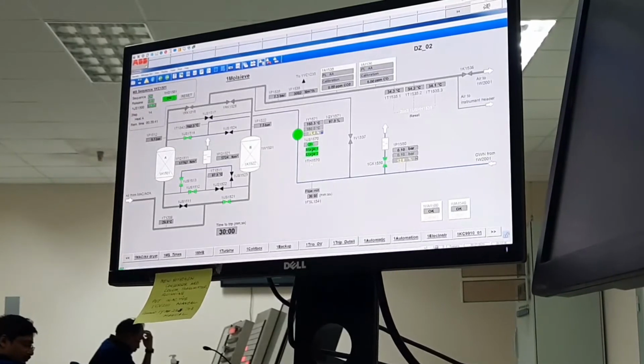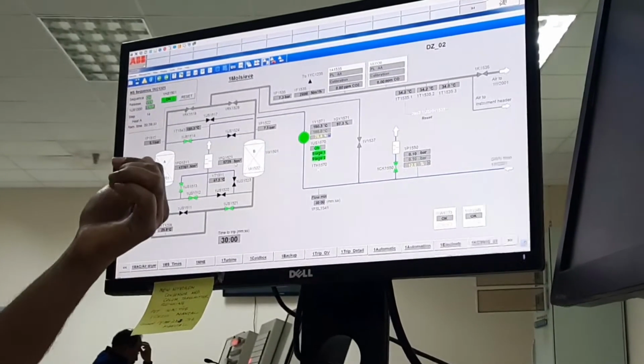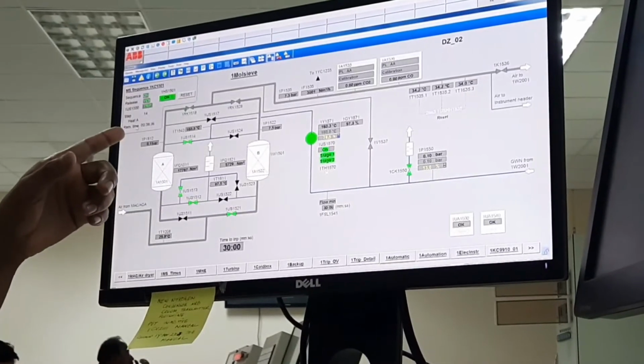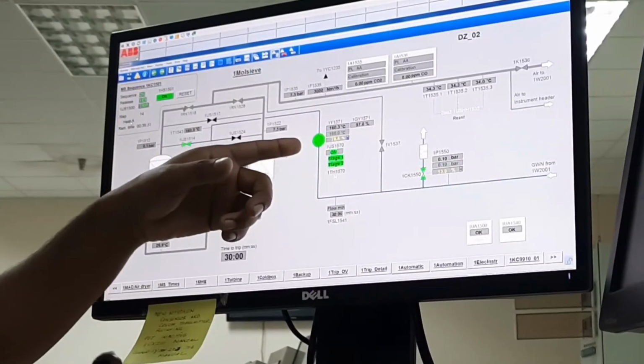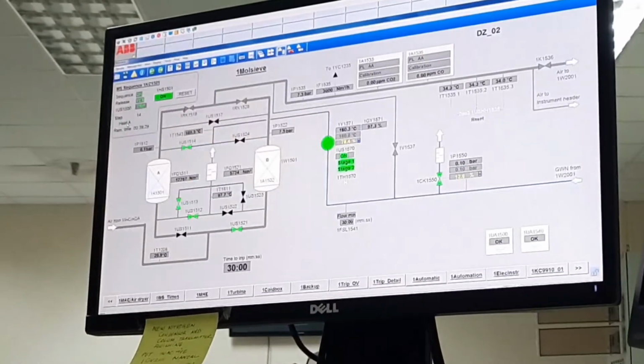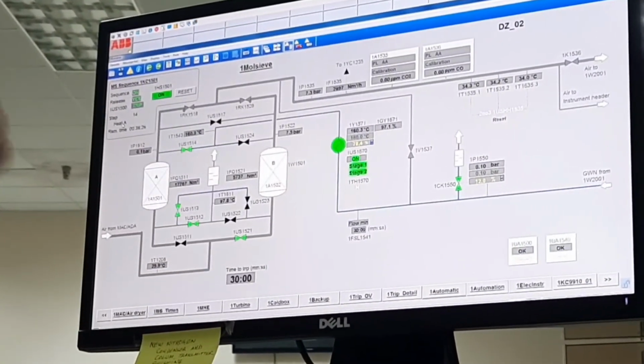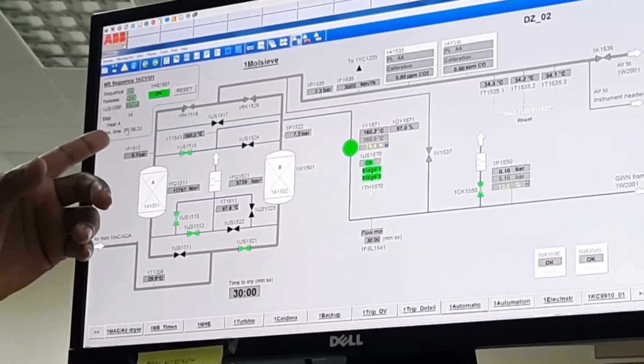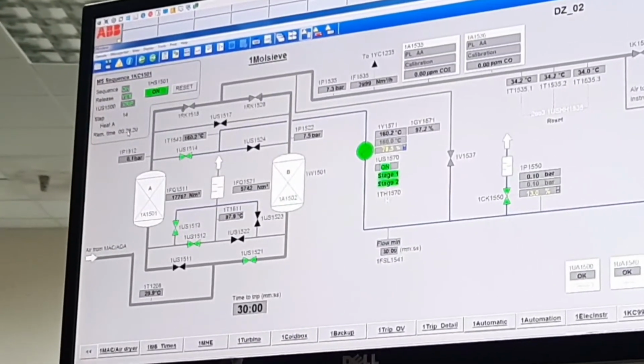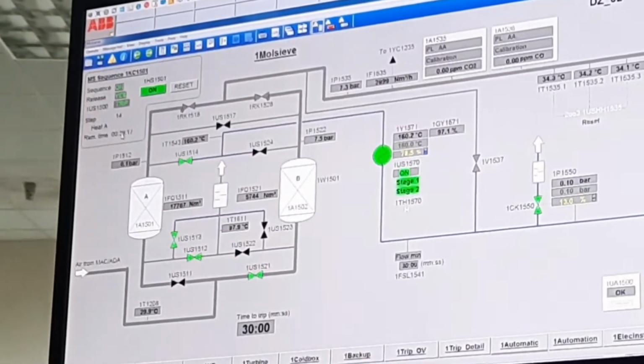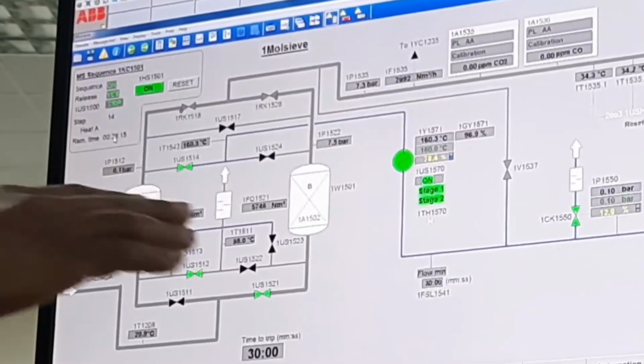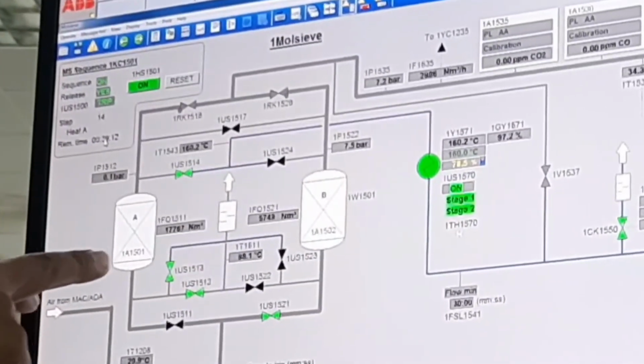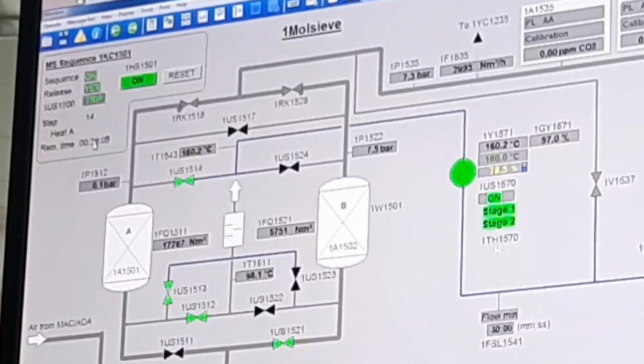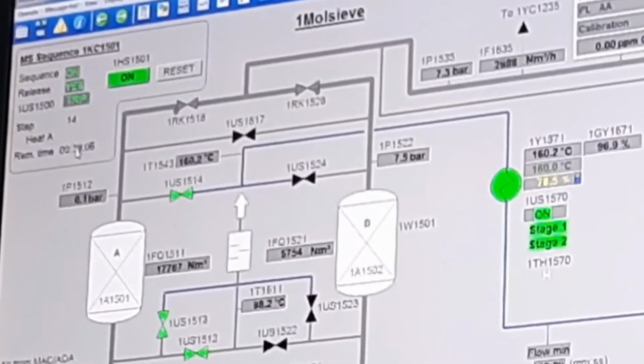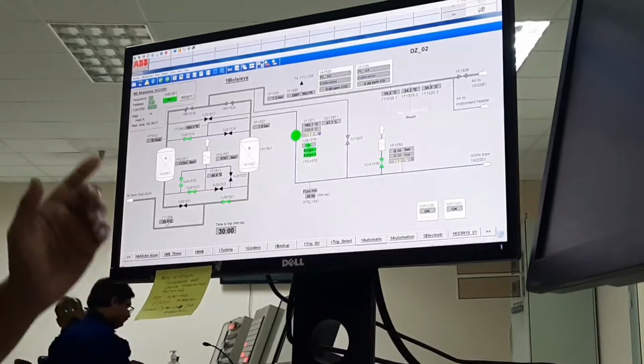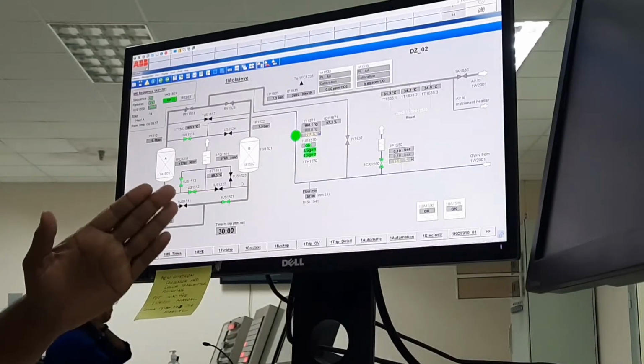Okay, clear. So now these vessels are in service condition, these vessels are in regeneration condition. You can see also this timer. Now it is heating condition, for that reason the heater is on. When cooling comes, the heater automatically will be off. Okay, stop. So now 39 minutes remaining for completion of heating. After heating, again I start cooling. After 3 hours, it will change over. That time one will go to service, one will go to regeneration. Clear? Any confusion?